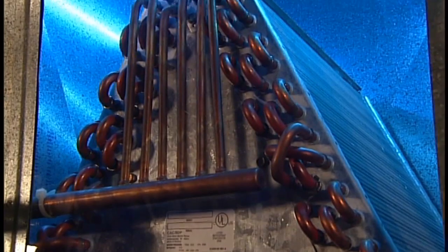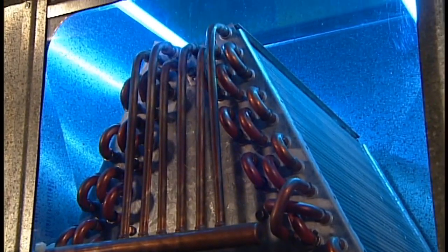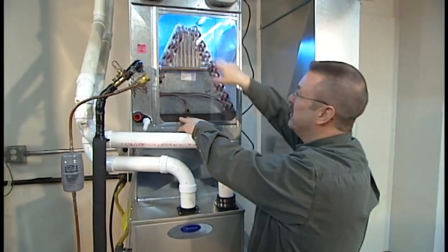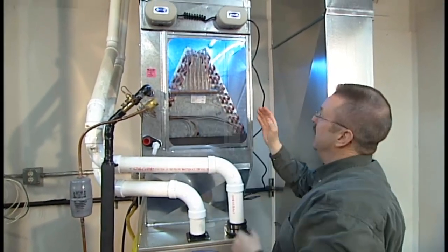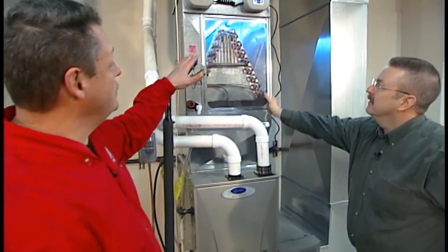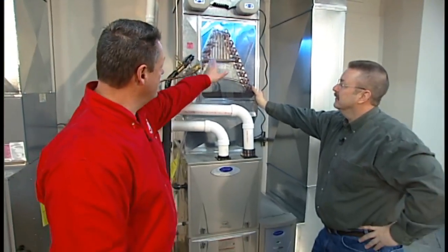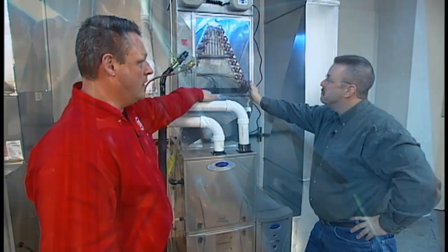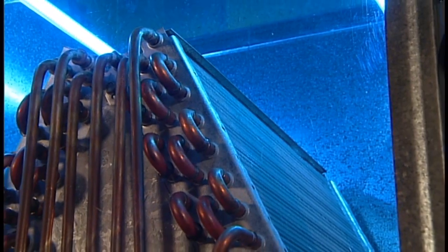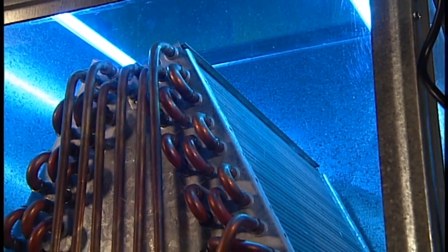Things I love about visiting your training facility: you get to see where you normally don't. And by that I mean, here's a plenum, you get to see the A coil for the air conditioning system. And I also notice a couple blue lights up there. Yeah, those are actually UV lights that radiate onto the coil and the condensate pan to kill microbes that can grow on there, which does two things: keeps it cleaner, higher efficiency.